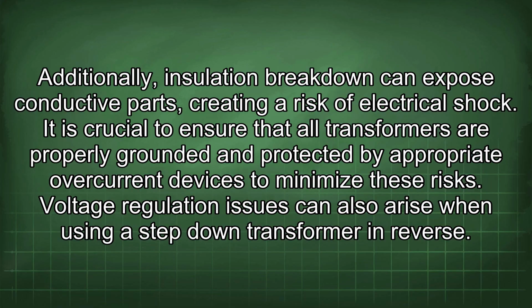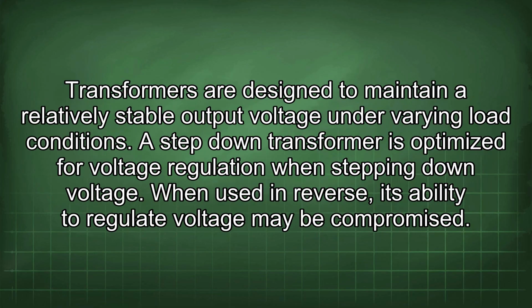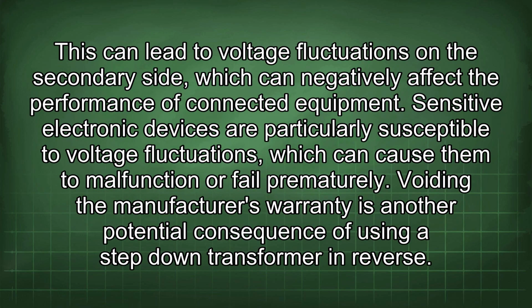It is crucial to ensure that all transformers are properly grounded and protected by appropriate overcurrent devices to minimize these risks. Voltage regulation issues can also arise when using a step-down transformer in reverse. Transformers are designed to maintain a relatively stable output voltage under varying load conditions. A step-down transformer is optimized for voltage regulation when stepping down voltage. When used in reverse, its ability to regulate voltage may be compromised. This can lead to voltage fluctuations on the secondary side, which can negatively affect the performance of connected equipment. Sensitive electronic devices are particularly susceptible to voltage fluctuations, which can cause them to malfunction or fail prematurely.